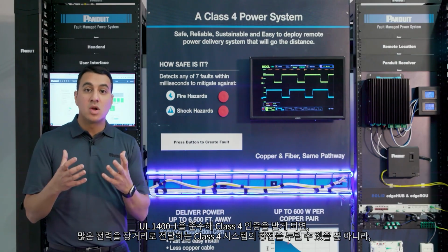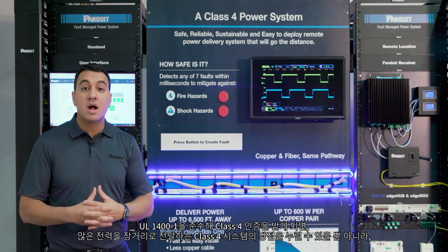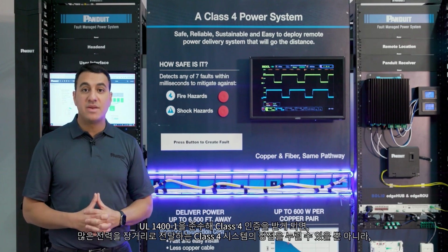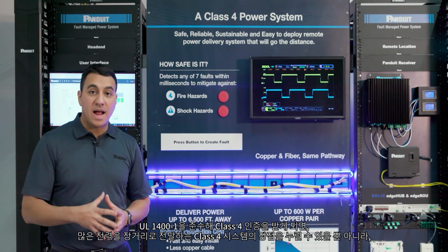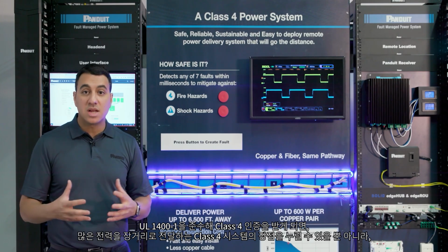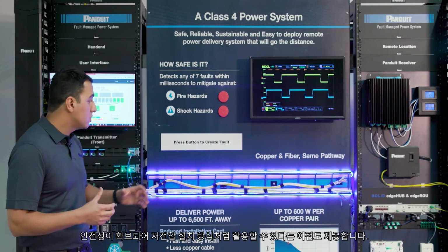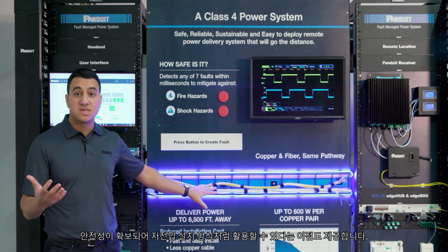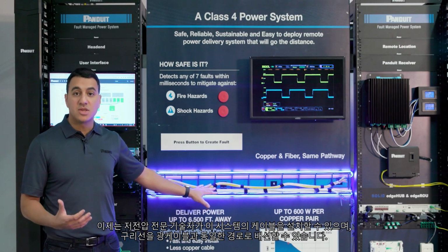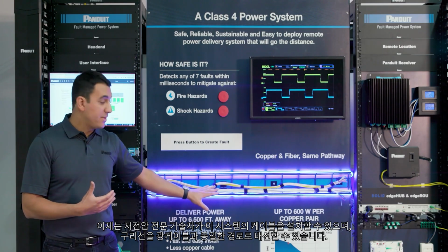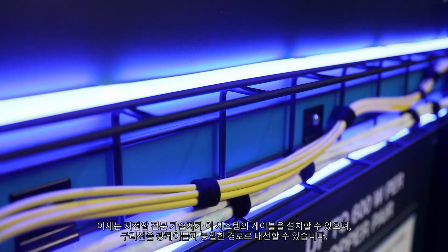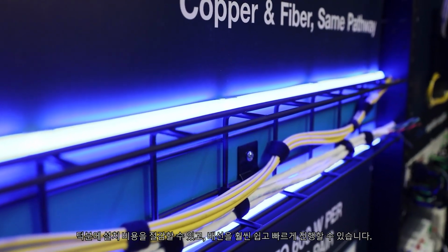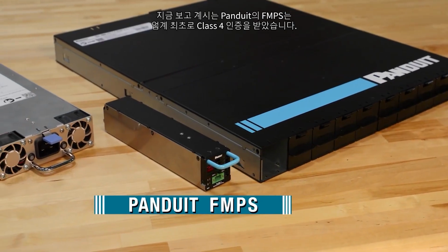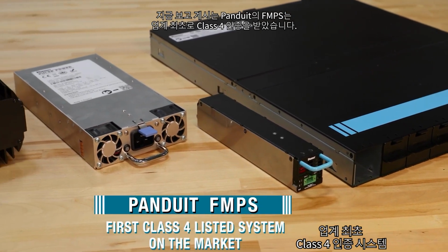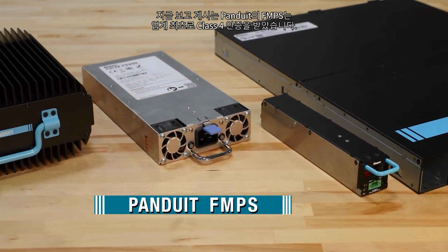The ability to comply with UL 1400-1 and become Class 4 listed now gives you the benefit of being able to push a lot of power and go long distance using a Class 4 system, but you can also leverage it as a low voltage installation because it's safe. So now you can have a low voltage contractor pull the cable for the system and run your copper in the same pathways as your fiber, saving on installation and making it easier and quicker to deploy. You're looking at the Panduit Fault Managed Power System, FMPS, the first Class 4 listed system in the market.